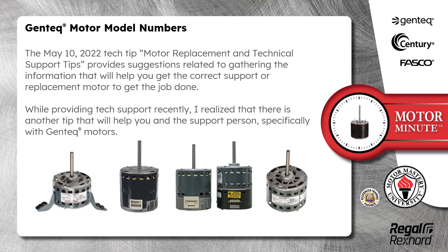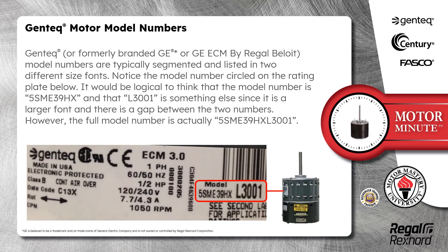While providing tech support recently, I realized there is another tip that will help you and the support person, specifically with Genteq Motors. Genteq — or formerly branded GE or GE ECM by Regal Beloit — model numbers are typically segmented and listed in two different size fonts. Notice the model number circled on the rating plate below. It would be logical to think that the model number is 5SME39HX and that L3001 is something else, since it is a larger font and there is a gap between the two numbers. However, the full model number is actually 5SME39HXL3001.